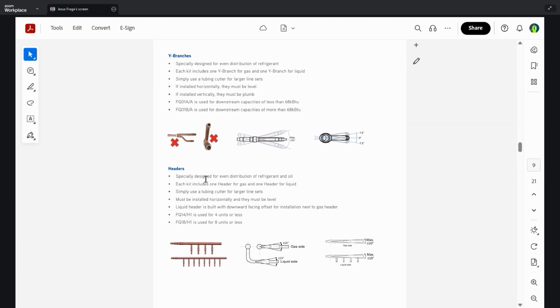So moving on to headers, they are specifically designed for even distribution of refrigerant and oil. Each kit includes one header for gas and one header for liquid. And same thing as the Y branches, simply use a tubing cutter for larger line sets. Must be installed horizontally and they must be level. Liquid header is built with downward facing offset for installation next to gas header, as we illustrated here in this picture. So this is the L shape of the liquid line, and the gas will sit on top of it if you choose to install it that way. As long as they're horizontal, you don't have to necessarily do this, but they are designed to fit right on top of one another.